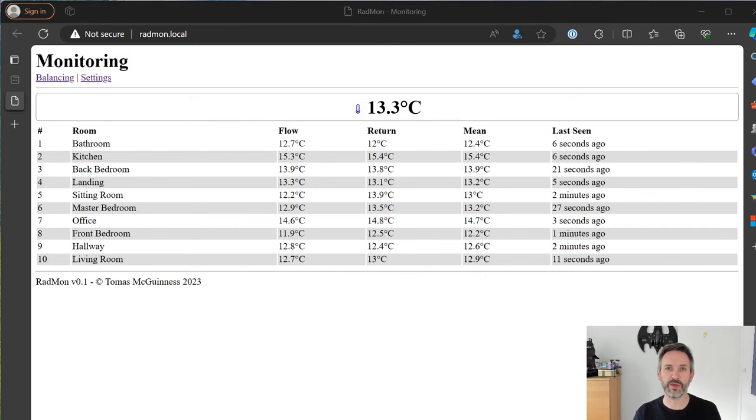So to help me figure out whether or not these are accurate, I've picked up two professional measurement clamps. They're from a company called Testo and they make a range of all sorts of instrumentation to do with the heating industry. I visited them at the installer show earlier this year and spied that they had a simple Bluetooth clamp. They're quite popular among professionals in the industry. They use them for checking delta Ts across all manner of things. So I splurged and I picked up two of them with the plan of using them to calibrate my own sensors.